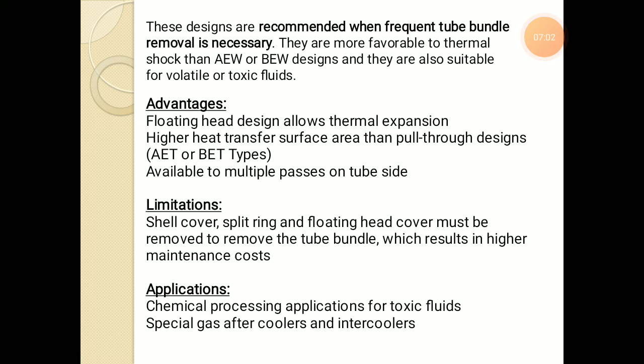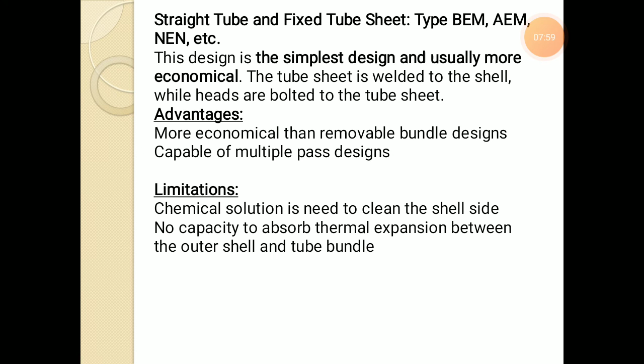Next one, straight tube and fixed tube sheet type, BEM, AEM, NEN. This design is the simplest and usually more economical. The tube sheet is welded to the shell while the heads are bolted to the tube sheet. Advantages of this straight tube and fixed tube sheet design: it is more economical than removable bundle design, and it is capable of multiple pass design. Limitation: chemical solution is needed to clean the shell side, and there is no capacity to absorb thermal expansion between the outer shell and tube bundle.